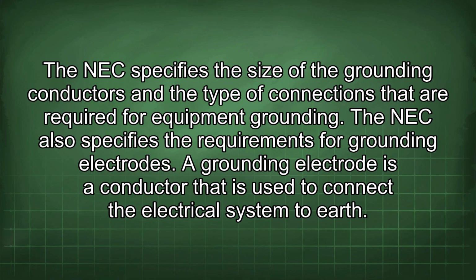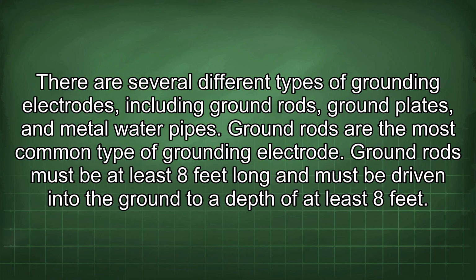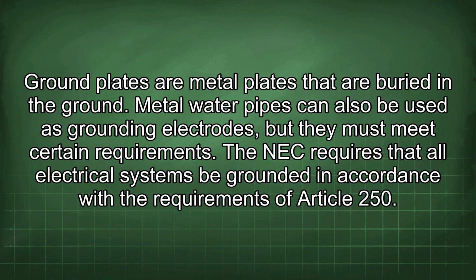A grounding electrode is a conductor that is used to connect the electrical system to earth. There are several different types of grounding electrodes, including ground rods, ground plates, and metal water pipes. Ground rods are the most common type of grounding electrode. Ground rods must be at least 8 feet long and must be driven into the ground to a depth of at least 8 feet. Ground plates are metal plates that are buried in the ground. Metal water pipes can also be used as grounding electrodes, but they must meet certain requirements.